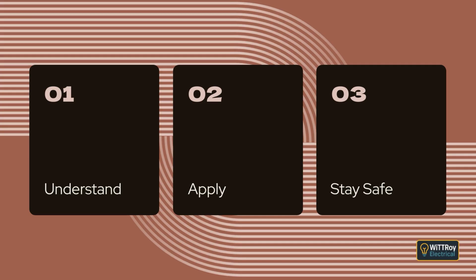Clause 7.2.7.1, General. This clause explains that wiring systems supplying safety services must be able to keep supplying the equipment when exposed to fire. Clause 7.2.7.2, Type of wiring. This clause explains that wiring systems supplying safety services, including consumers' mains, must comply with AS/NZS 3013 with a WS classification or the classification given in the standard applying to the installation. The note refers to Appendix H for more detail on the WS system.